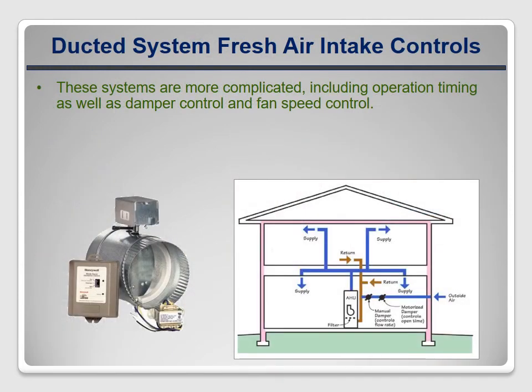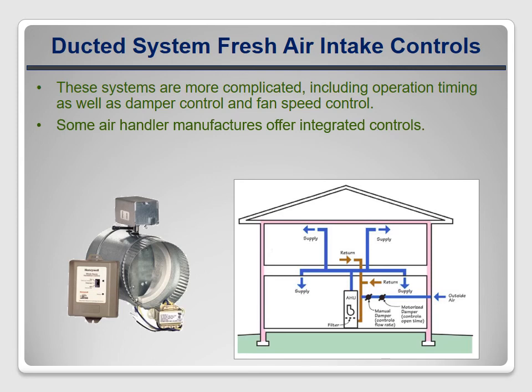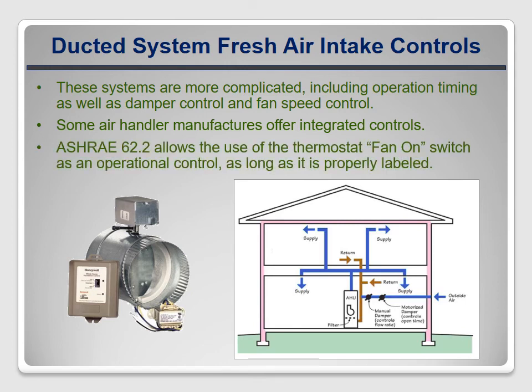Controls for fresh air intakes and ducted systems are more complicated. They may cycle the air handler on at full speed, or they may cycle it using a lower speed tap for ventilation. With some new variable speed systems, they may electronically reduce the fan speed to a very low level so it's quiet and energy efficient. Numerous controls are available — some are add-ons, and some are made by the air handler manufacturers for easier integration with the heating and cooling controls. ASHRAE 62.2 specifically allows the use of the thermostat fan on switch as a means for the occupants to control the system, as long as its function is clearly labeled.